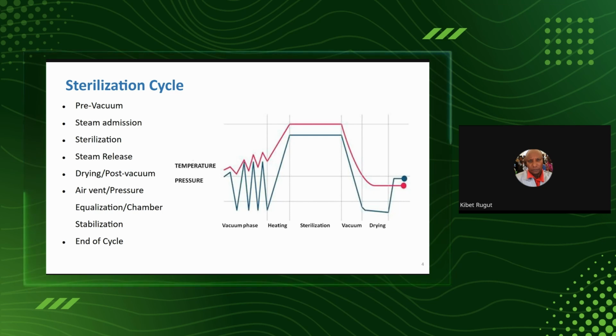Then the sterilization itself is a length of time that is determined depending on the goods you are sterilizing. And then from there, there is a huge volume of items and some linen. So you might find that steam could have also lost its temperature or dryness. Some humidity might have gone in. So you have another cycle just to ensure that everything is fully dry, which is you suck out anything that has not been released in the chamber, and then you dry the equipment. Once you do that, the vacuum and the pressure are balanced so that the door can open easily. And then you go to the cycle end.